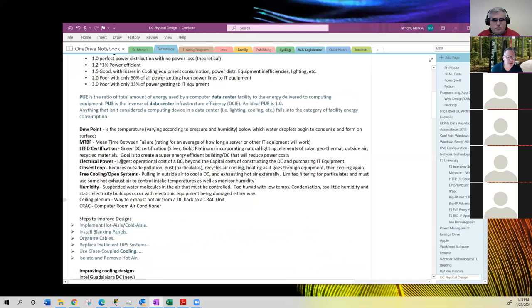We talked about power being the largest operational cost in a data center, beyond even the data center purchase, build, and IT equipment. We talked about closed loop and open loop. Open loop can be free cooling, as they call it. And we also talked about the ceiling plenum, the area where you run hot air back to be cooled in a closed loop. It's also where wiring and power go. You have to have power and data, copper data cables, at least a foot apart.